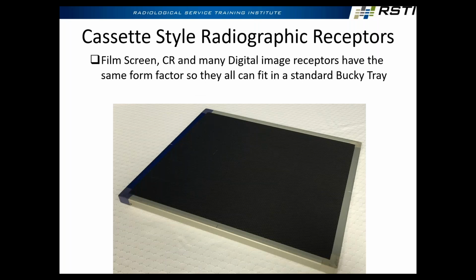CR cassettes you may have heard of, or these are like a flat panel that's portable. The advantage with these is they can retrofit and go into a Bucky. So if you want to take a system that was analog only and convert to digital, you could use a CR cassette or a wireless detector that will fit into a standard Bucky. So a lot of systems now use wireless detectors like this. Remember, the Buckys could be a table or in the wall stand. So this one detector could be used in a table for one exposure, then moved to the wall stand for a chest shot, the same detector. They could even take that detector to the next room over and use it in multiple rooms.